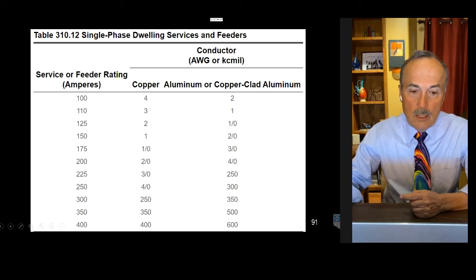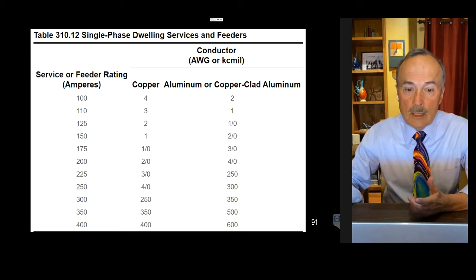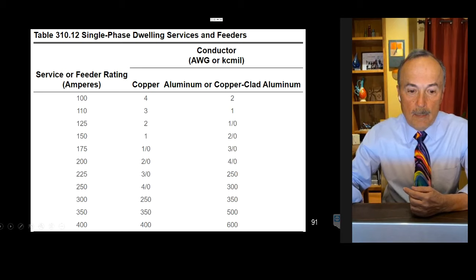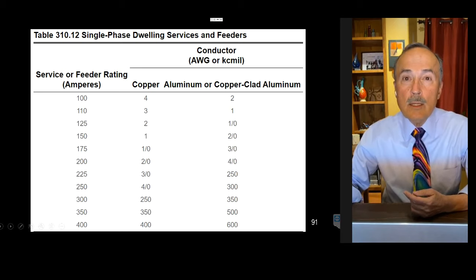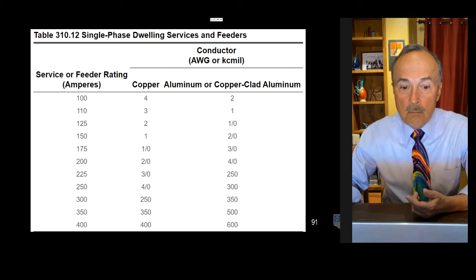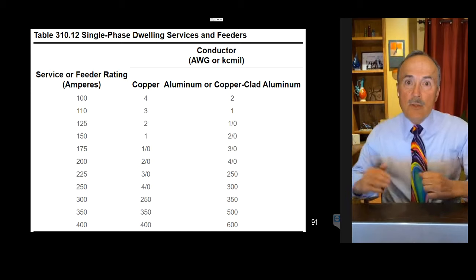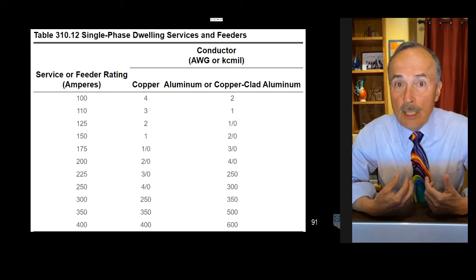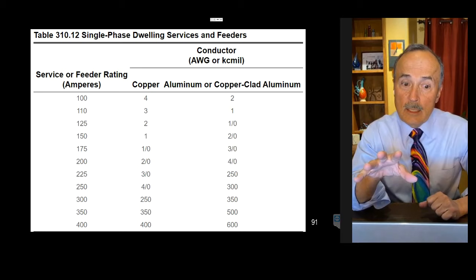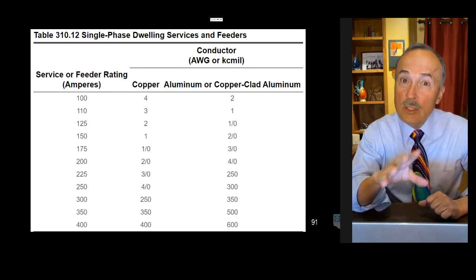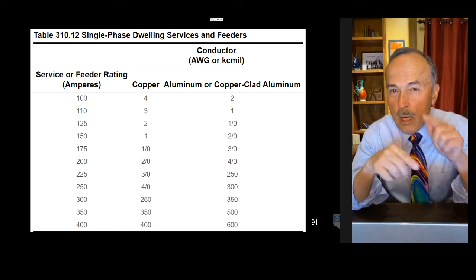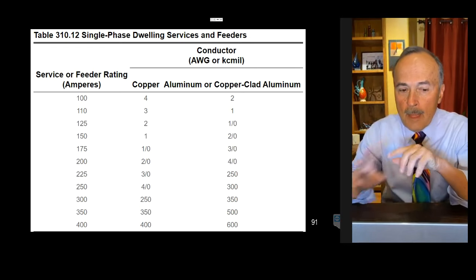So what they did was they took the table and went in reverse, and this table is 83% of the service rating. In other words, let's go to a 200 amp service. You can use 83% of 200 amperes, which is what, 166? I think it's 166 or something like that. Well, then you go to 2/0 AWG, and I think 2/0 AWG is rated 175. Everybody's fine. So they got rid of the table to use the 83%.